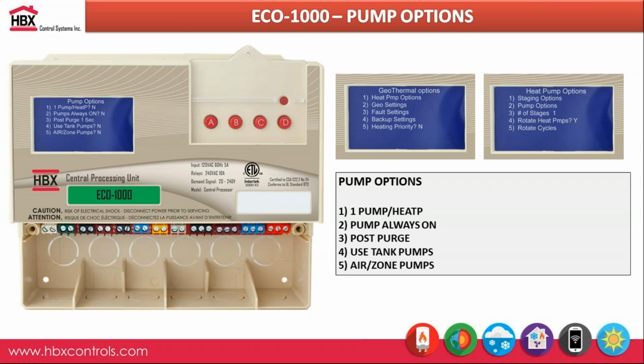You can use the controller to control tank pumps, so it doesn't have to be the main system circulators. We can control that hot tank and cold tank pump right off the controller, as well as on the expansion modules. And then you have the option to use air to zone pumps on the controller. So if you wanted to control the pump for a fan coil, you can do that off the P1 terminal. Anything that comes off in terms of a heating or cooling demand, it'll come off that P2 pump controller off the Eco 1000 for your zone pump options on there.